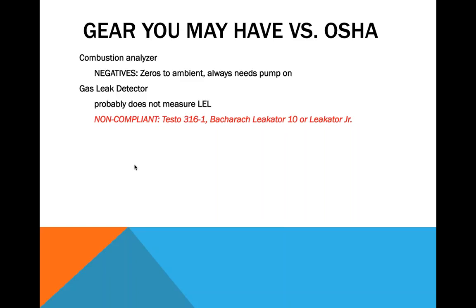The gas leak detector that you might have probably does not measure LEL, or lower explosive limit. Non-compliant products with this phrase about measuring LEL: the Testo 316-1, the Bacharach Leakator 10, or the Leakator Junior by Bacharach. None of those actually measure the lower explosive limit. They detect relative changes. But in order to make a measurement, you need a more refined device, and we'll be talking about those in a moment, some specific brands that we carry.